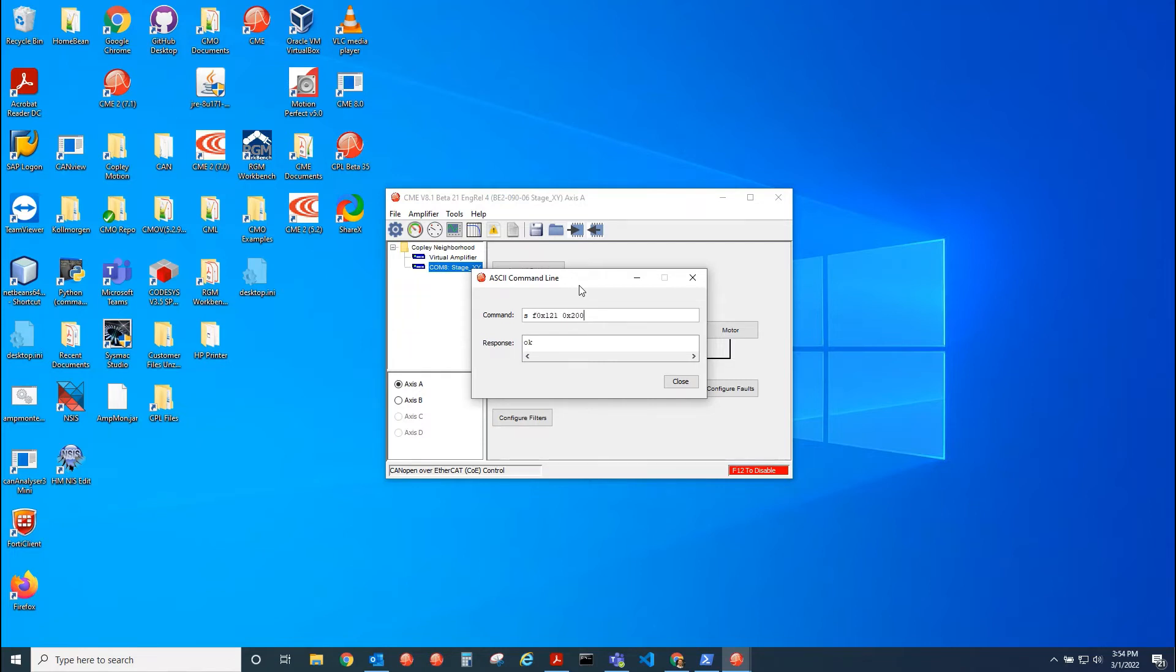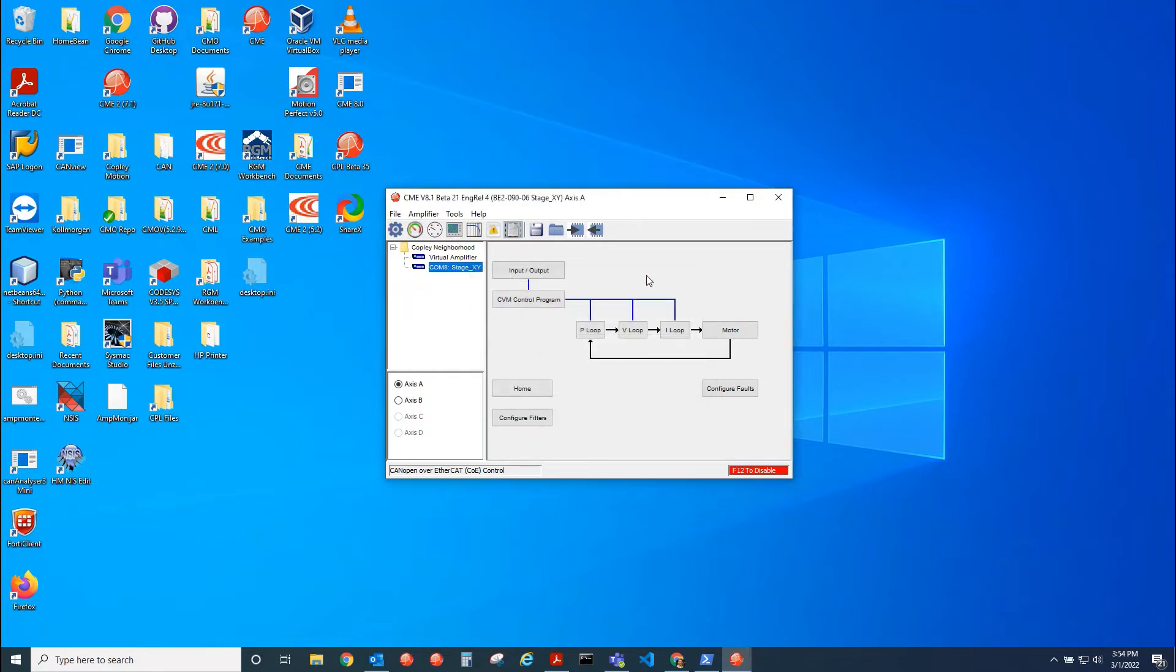So now UDP is enabled because I have EtherCAT firmware inside the drive, but I've set bit nine of parameter 121, the network options parameter.